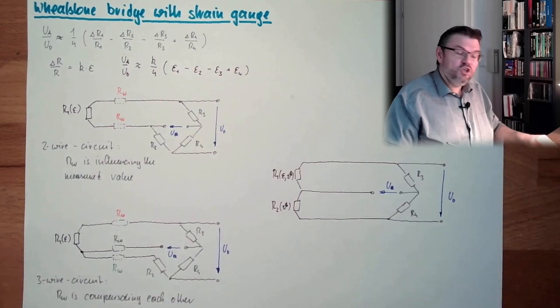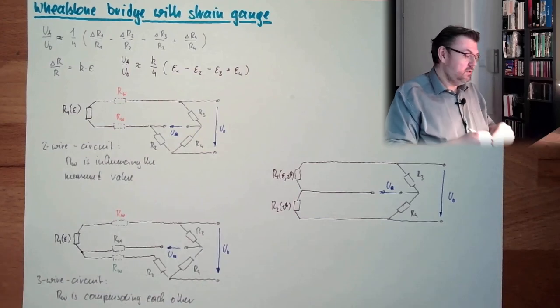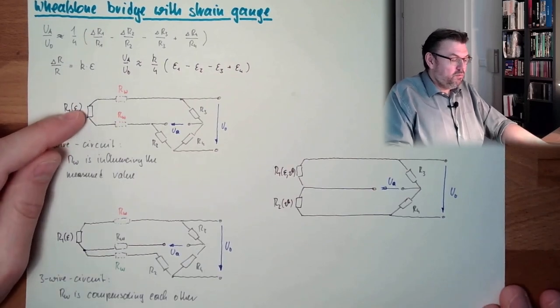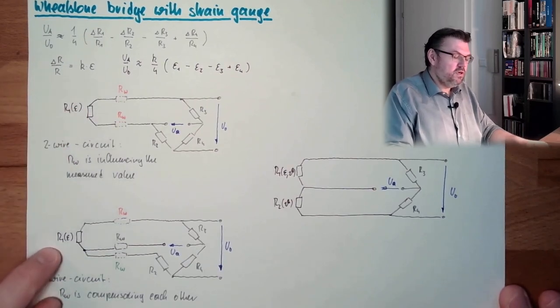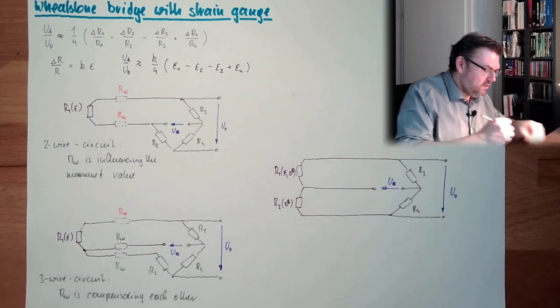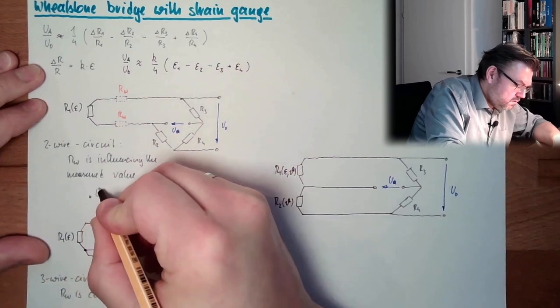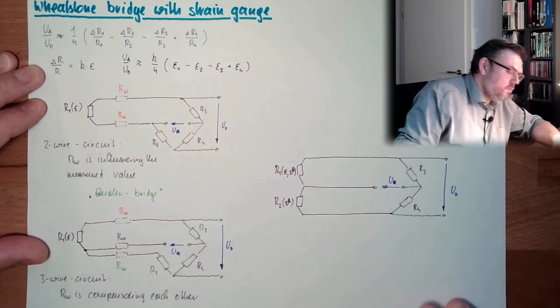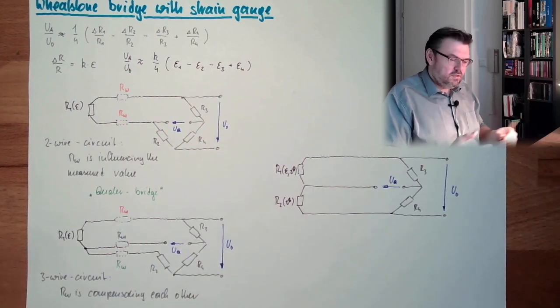And the heat is influencing R2 negatively, so the heat effects compensate each other. This is called a quarter bridge in two-wire connection, or a quarter bridge in three-wire connection. These are quarter bridges. And this is a half bridge.